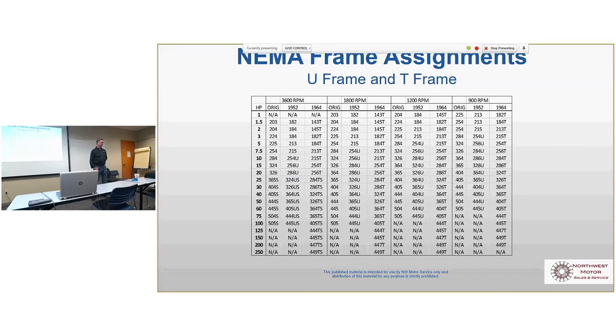So you'll have a motor that's drilled for two frame sizes, right? A common one with a customer of mine is 200 horse 1800. It's drilled for a 445 and a 447 T frame. So the 2F, the length from front to rear holes, is something like 9 and 11. Well, there are some original installations where maybe somebody drilled to match the wrong sets of bolt holes, and so you'll find something that maybe is non-standard.